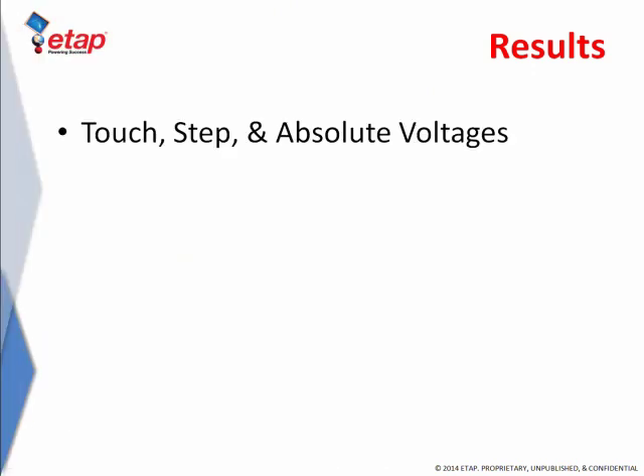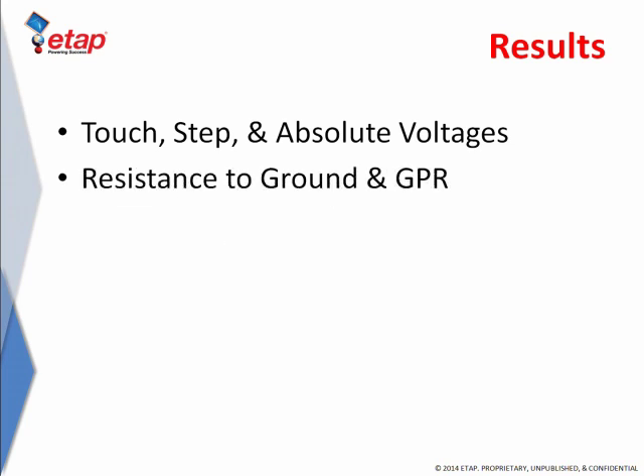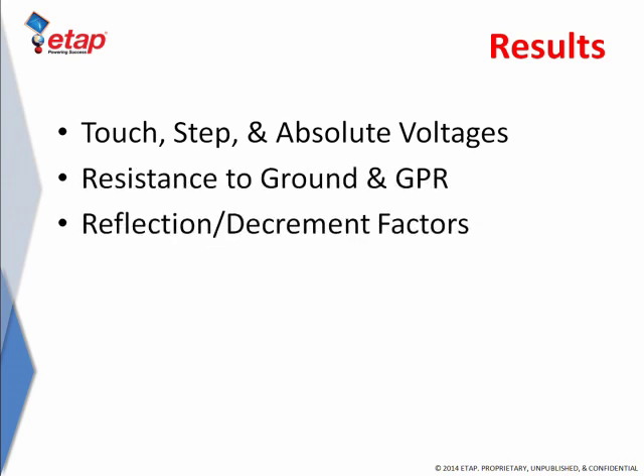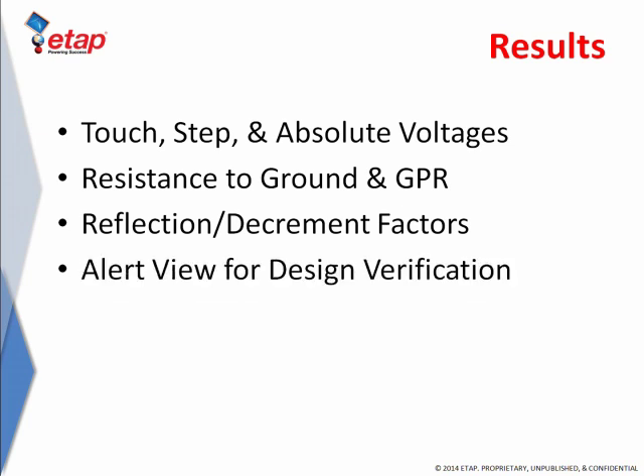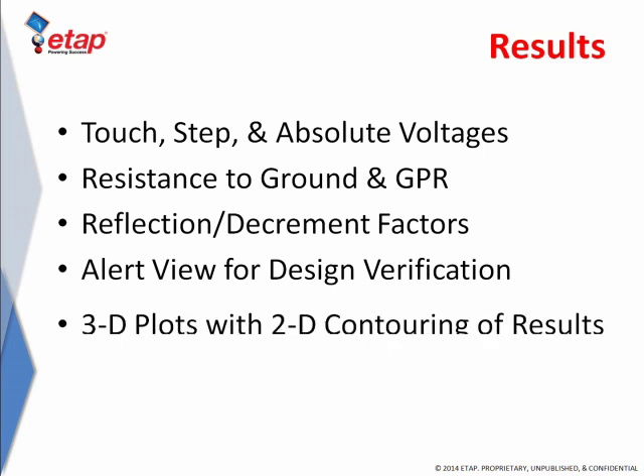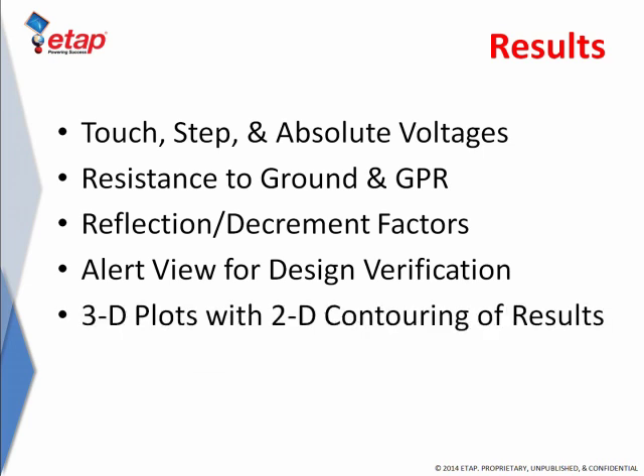Following the calculations, ETAP reports step and touch voltages, resistance to ground, ground potential rise, and reflection and decrement factors. ETAP automatically checks and reports any violations according to the tolerable limits and uses 3D plots with contouring capability to visualize the grid voltage profiles.